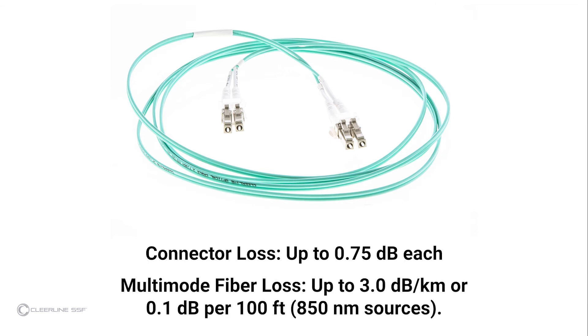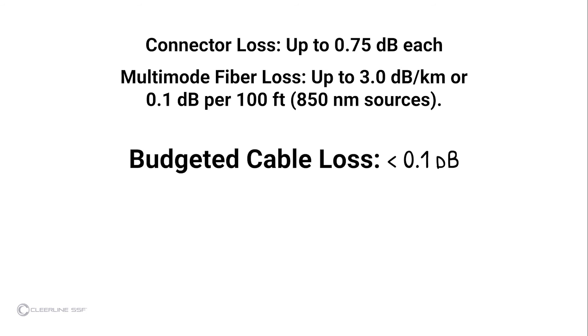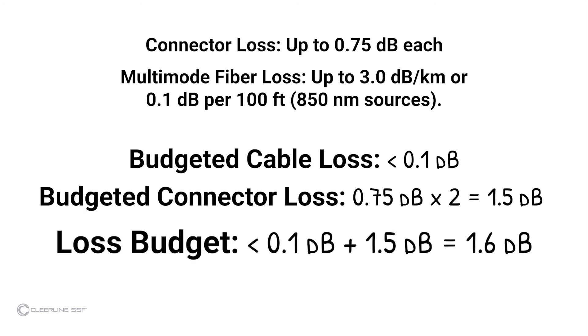Single-mode fiber loss is calculated at an average loss of 1.0 dB per kilometer for 1310 nanometer sources, or roughly 0.1 dB per 600 feet. For multimode fiber, the loss is about 3.0 dB per kilometer for 850 nanometer sources, or 0.1 dB per 100 feet. In this video, the cable under test is quite short, so the cable loss calculation is less than 0.1 dB. The loss calculation for the connectors is 1.5 dB (0.75 dB per connector times 2 connectors). The test result is less than 1.6 dB, so the cable passes industry standards for link loss.